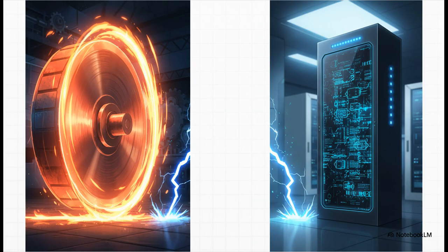And this is the absolute key takeaway. An inverter just does not respond to a fault the same way a big synchronous machine does. Its behavior isn't governed by physical inertia. It's dictated by software and control logic. All the old assumptions we've relied on for decades, they're pretty much out the window.